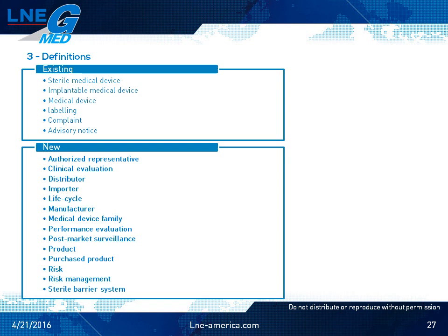To conclude with the elements that help understand and properly use the standard, we can identify that the definitions section has grown. In most cases, the definitions come from the former GHTF group. However, keep in mind that these definitions don't replace the regulatory ones. A regulatory definition always prevails over the one in the standard.